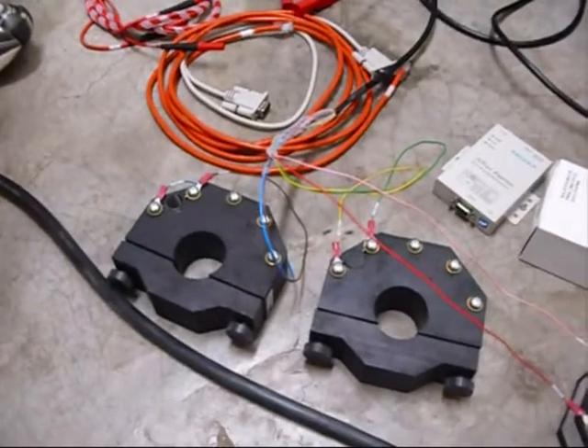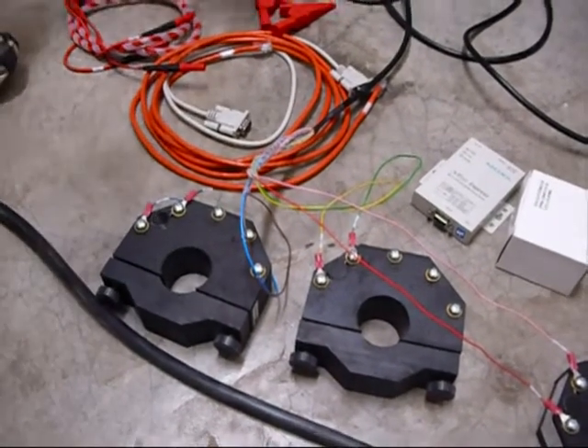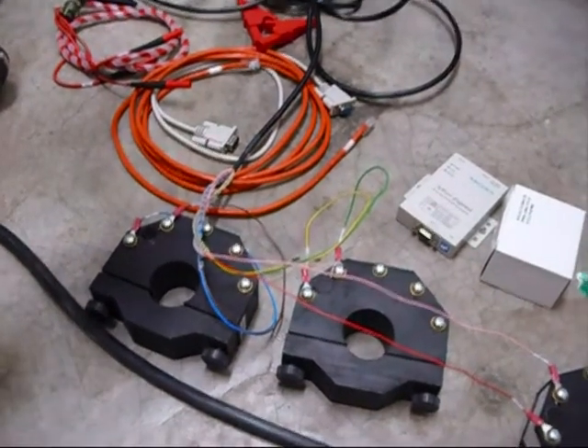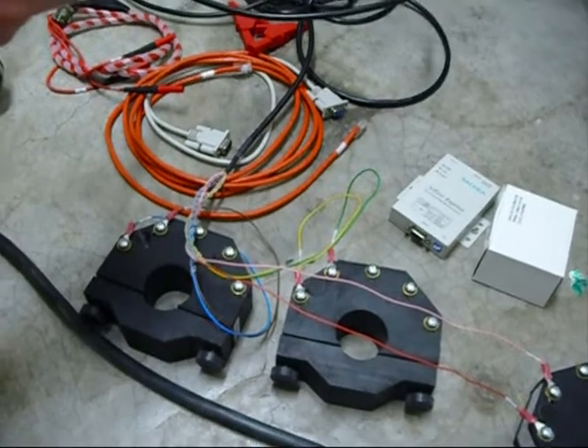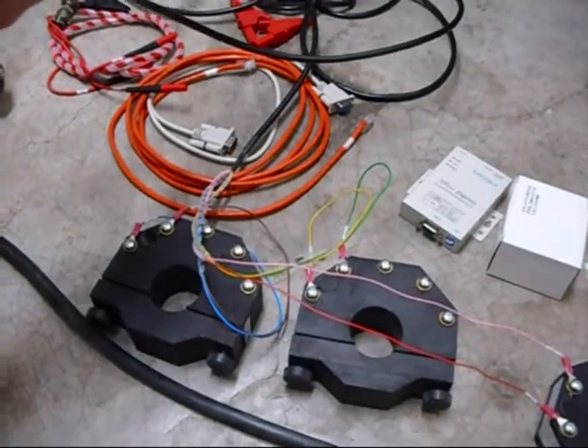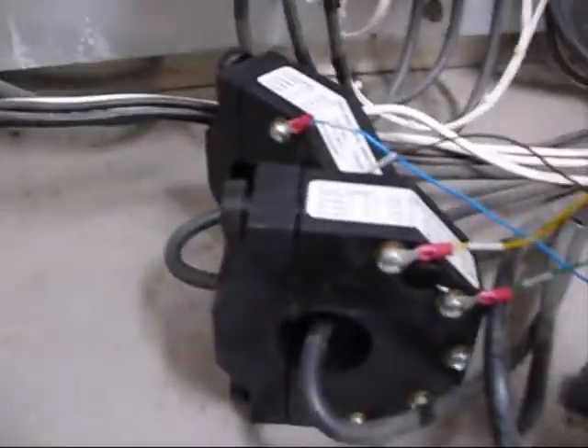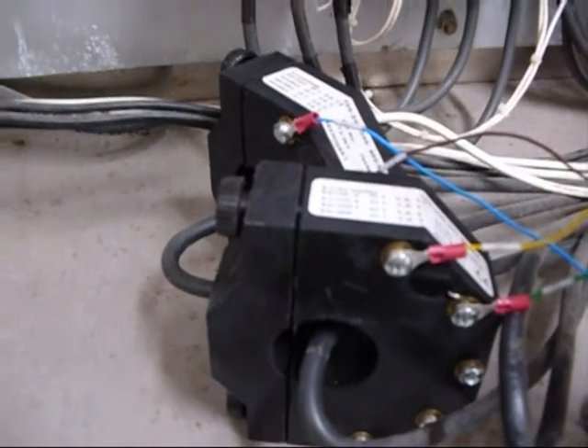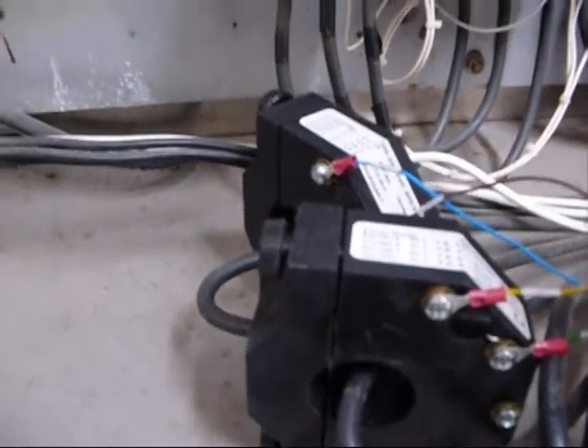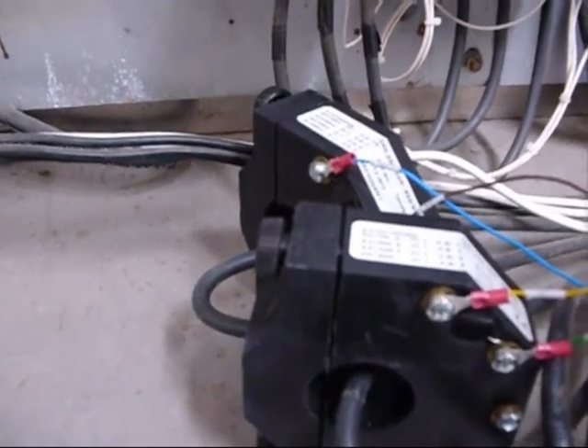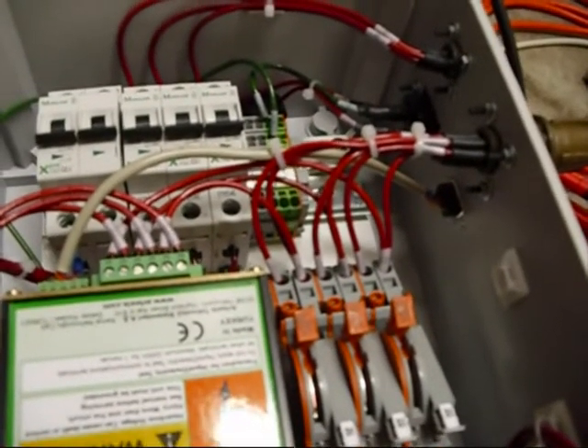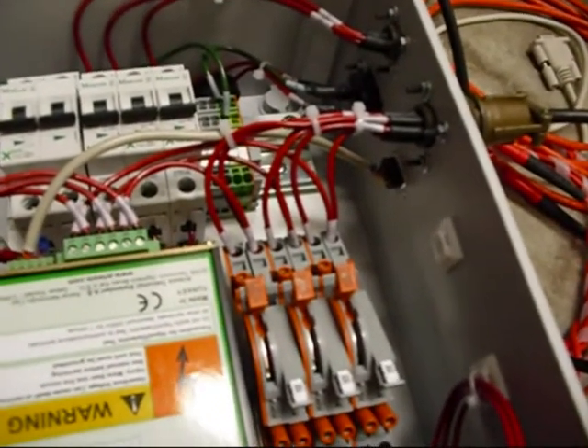What we're going to do is we're going to connect this CT cable to the unit and we're going to short the shorting links. Once we've done this, we're going to connect the CTs around the cables, and then when we power the unit up we will disconnect the shorting links. We now have 2 of the 3 CTs installed. The important thing in installing the CTs, we don't need the unit to be isolated to install the CTs, but what is absolutely necessary is to close the shorting links. As you can see here, when the shorting links are closed, they say open, they say test. If we close and make the connection live, you'll actually see the I11, I12 pairs shown. We'll show this in a bit more detail once we've installed the 3rd one.